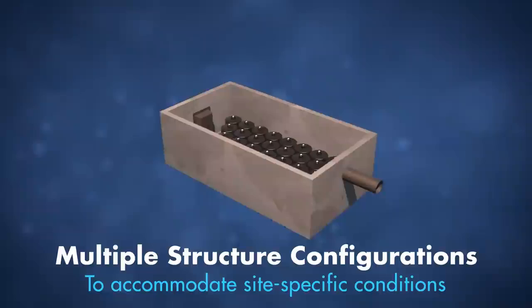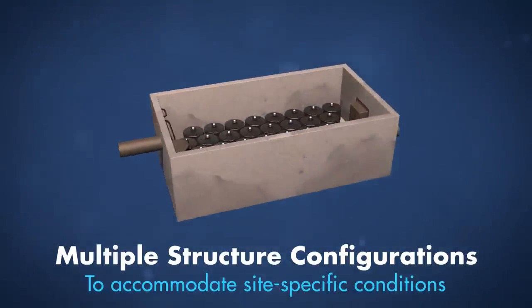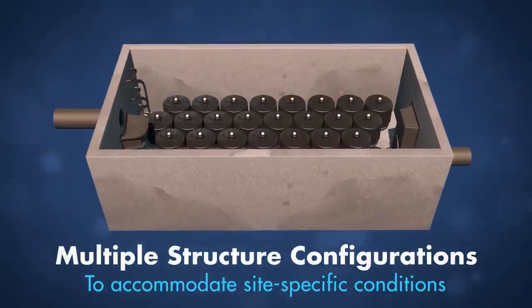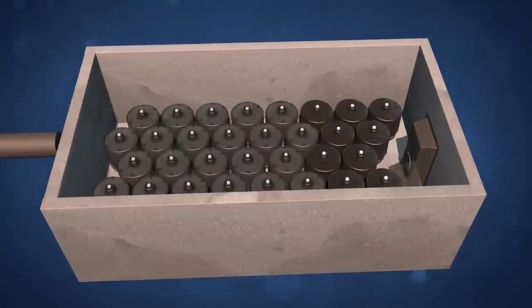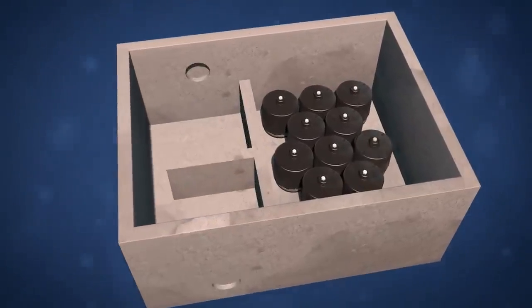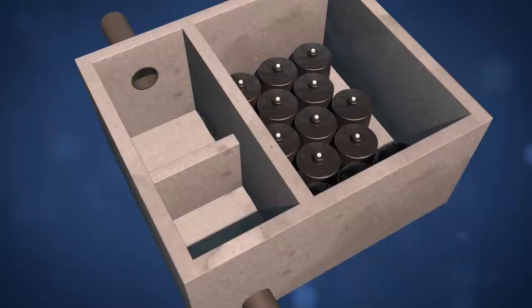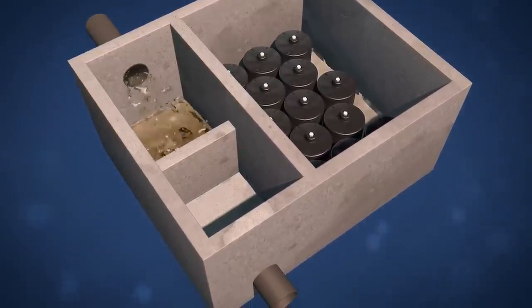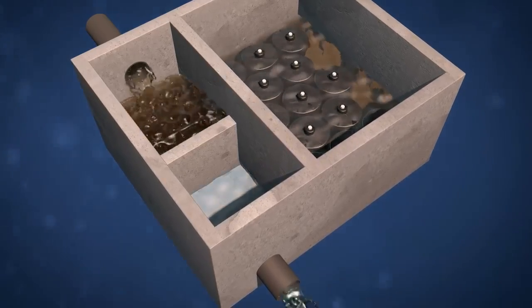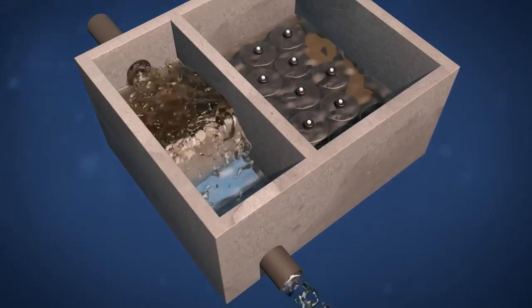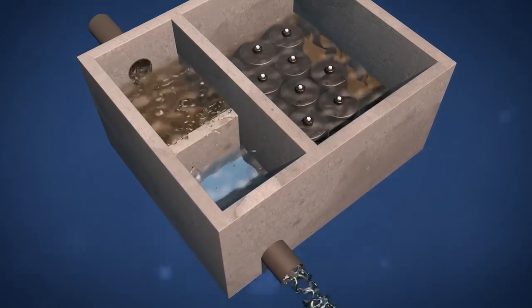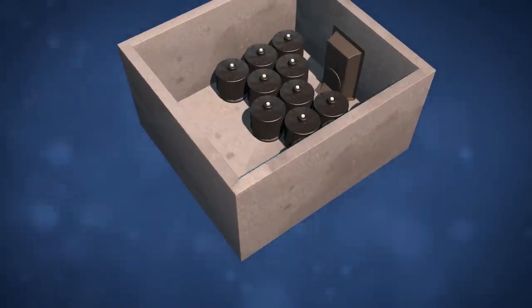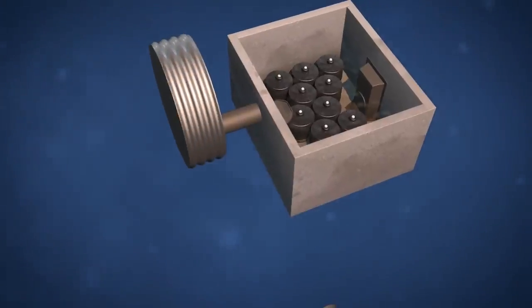The structures that house the filter cartridges can be configured in a variety of ways to accommodate a wide range of flows, project-specific footprints, and variable hydraulic conditions. The peak diversion storm filter provides high flow bypass and flow based treatment in one structure. Water enters the vault through an inlet and is directed to a treatment chamber containing the filter cartridges. During peak flows, the internal weir allows high flows to bypass treatment, eliminating the need for an external bypass structure.